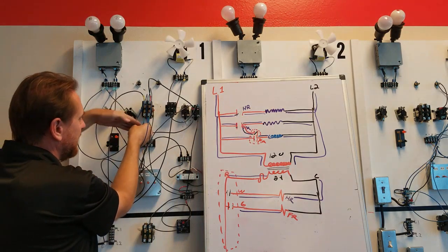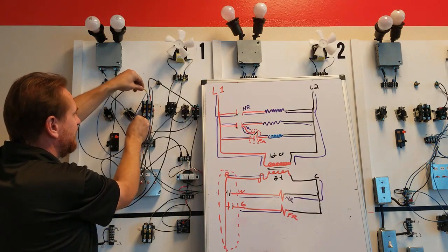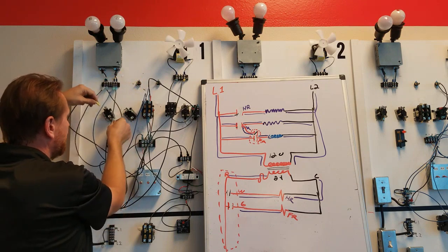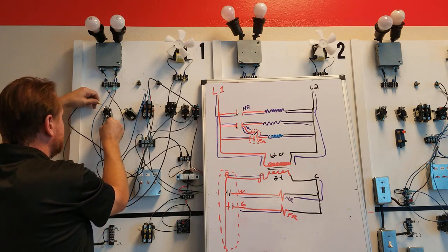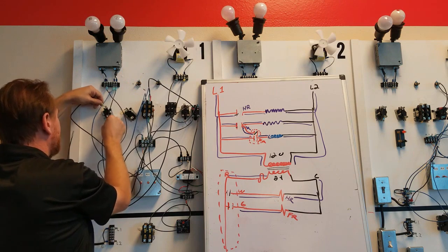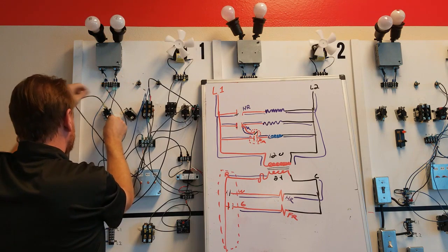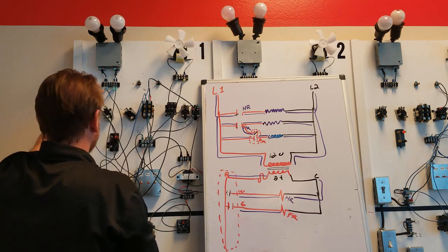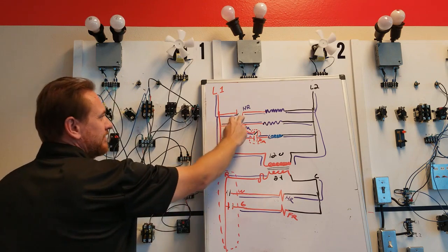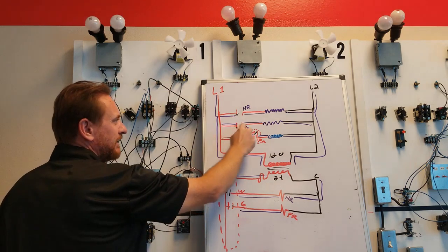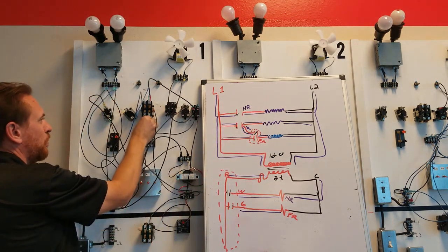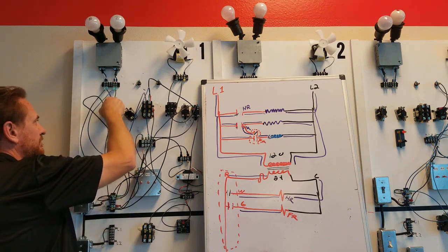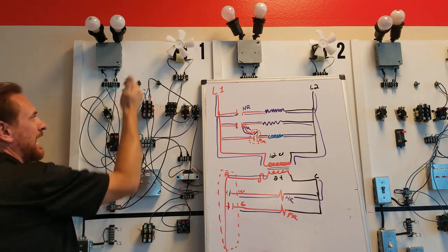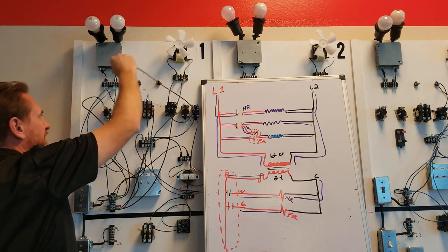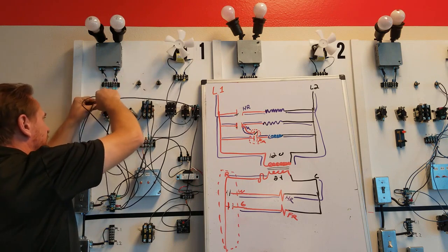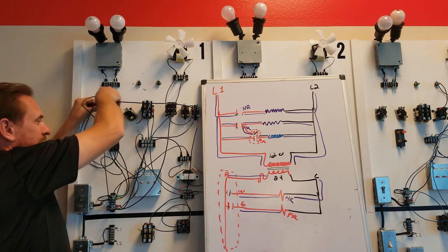Here I have one wire coming in, one wire coming out. So I'm going to disconnect these two, and I'm going to put them on the middle sets of terminal. One wire in, and one wire out. This one just fell off, which should never happen. So that one's done. Now I'm going to move down to this one, wire in and two wires out. Here we have one wire in. I'm going to put this in the very top. Coming out, two wires. I'm going to pull both these off together and put both of them on the opposite side. Now my high voltage is done.